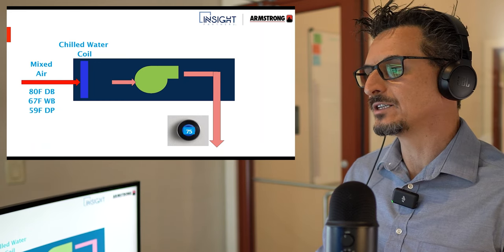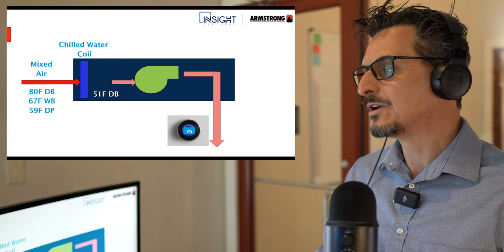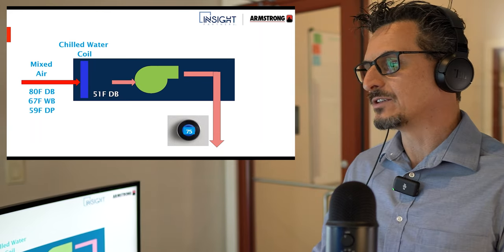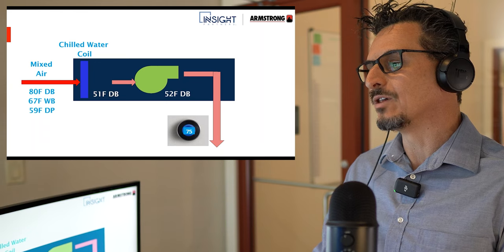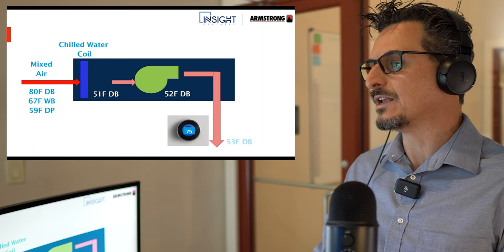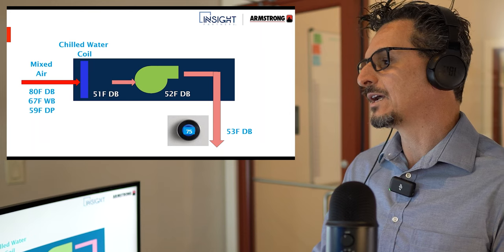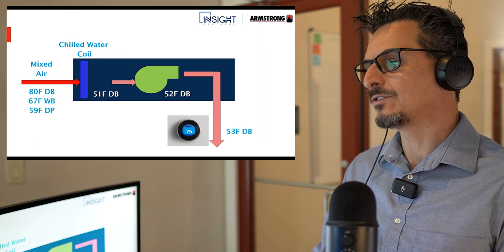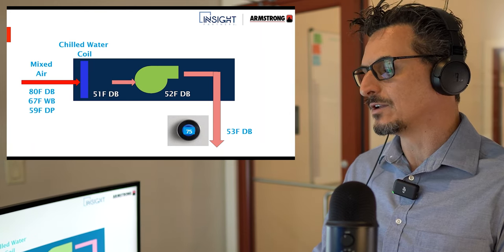You've got 80/67 entering the coil — that's your mixed air temperature. We decided we're going to enter the space at 53°F. So we're leaving the coil at 51, accounting for one degree of fan heat and one degree of duct heat. That gets us into the space at 53 degrees. This is a working model of a full load condition.